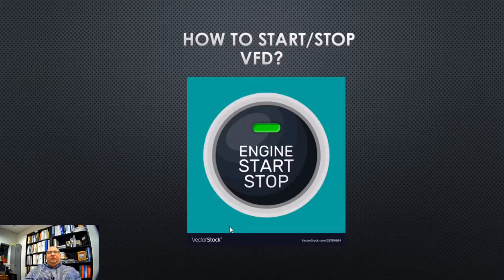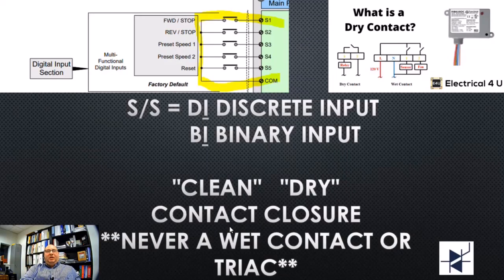So how do we start the VFD? We want to get it to work, right? We understand that we need to have the motor's information, the drive information, and now we have a bunch of terminals. What theory do we need to do to get this to operate? Well, the most common way to start the drive is to use a discrete input. You'll see me use either DI or BI. It all depends on who's writing the instruction manual.